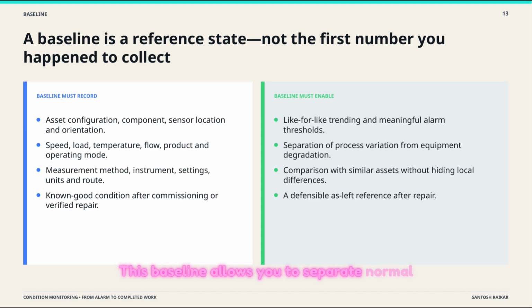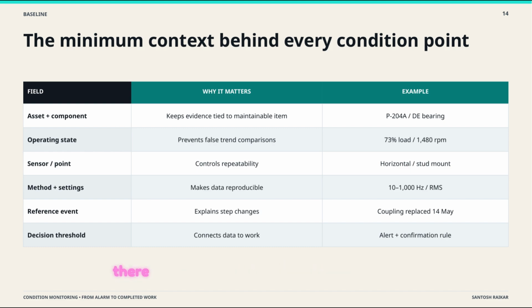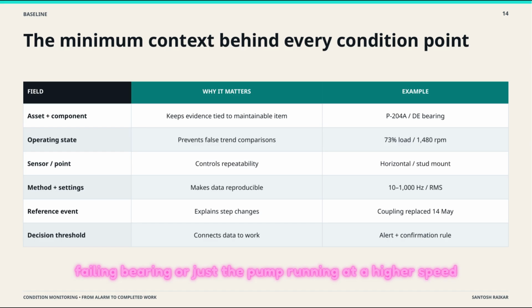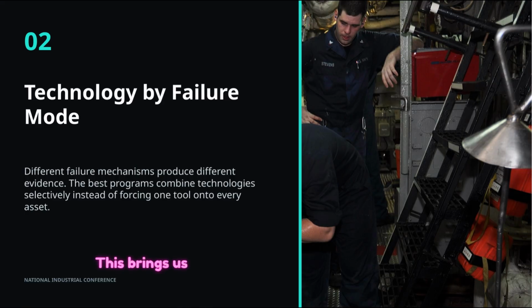This baseline allows you to separate normal process variation from actual equipment degradation. Behind every data point, there should be a minimum amount of context. We need to know which component we're looking at, the operating state, like 73% load, and the sensor settings. This context is what makes data reproducible. Without it, you can't tell if a vibration increase is a failing bearing or just the pump running at higher speed. This brings us to Act 2, selecting technology by failure mode.